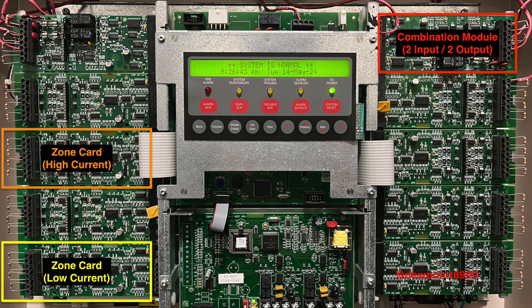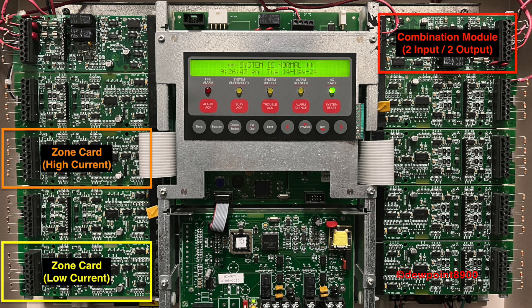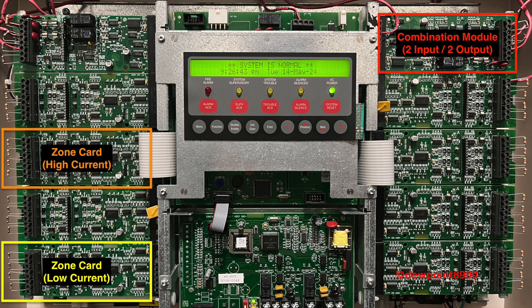The NAC relay card provides four outputs, configured as either NACs or relays. A combination card contains two zones and two NAC relays. Each of the previous cards explained will also accept a Class A adapter. Lastly, an 8IO card can be used for various appliances, such as the 46-1 series LED annunciator.